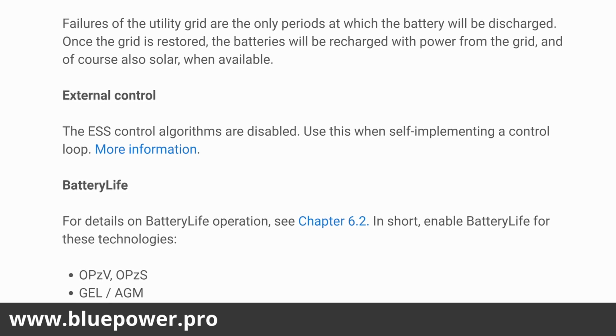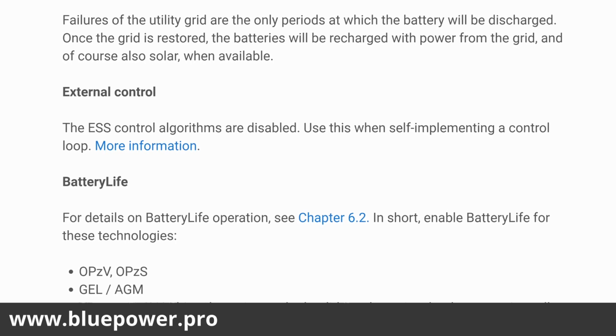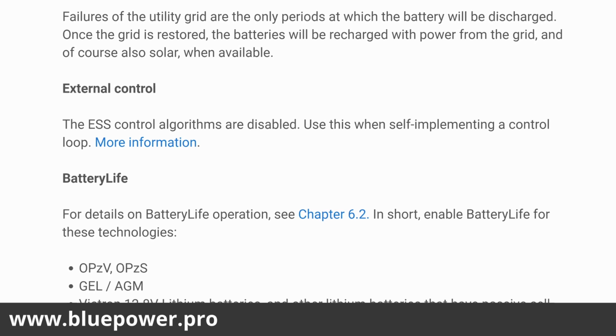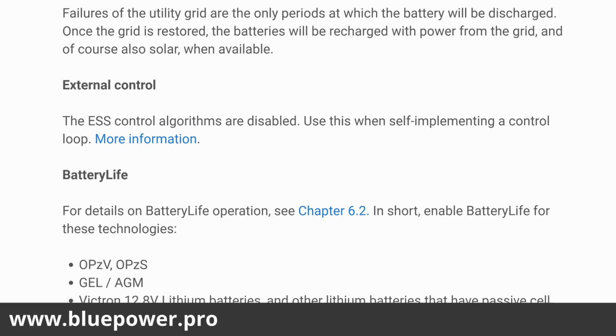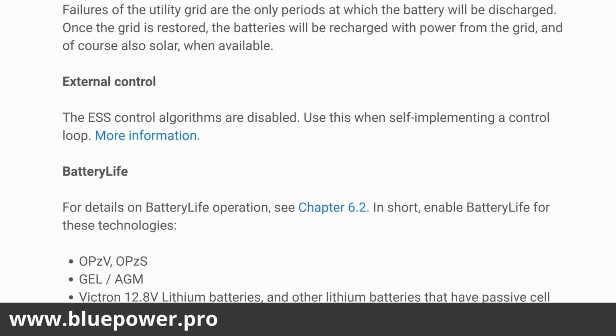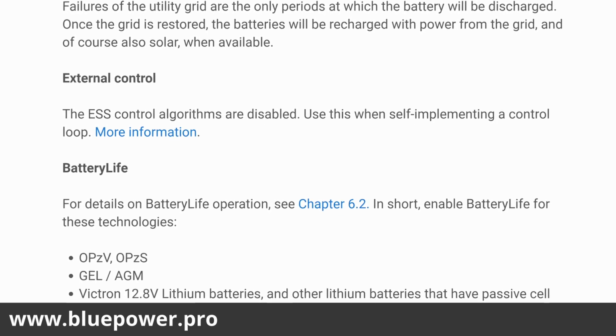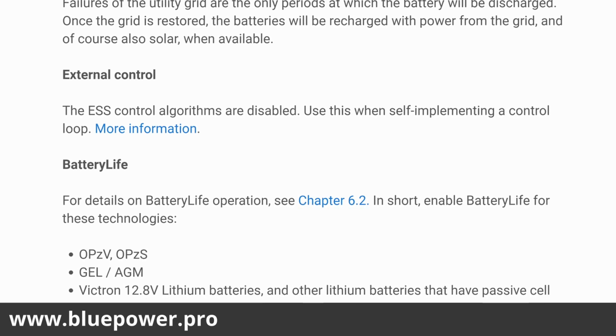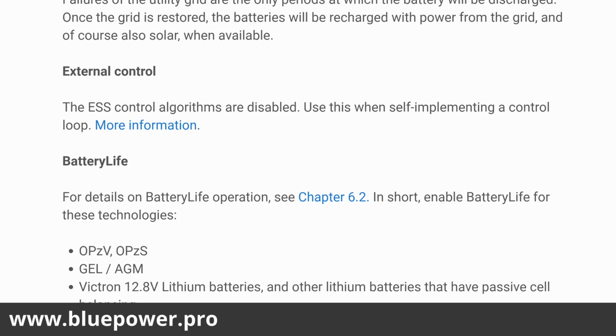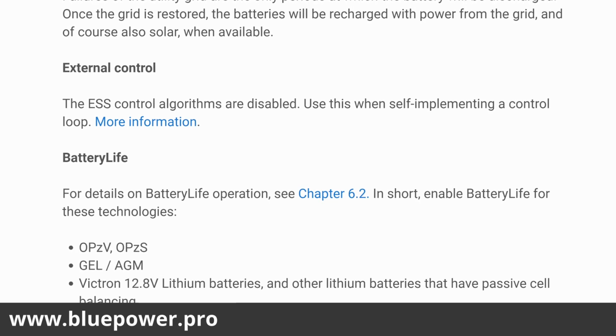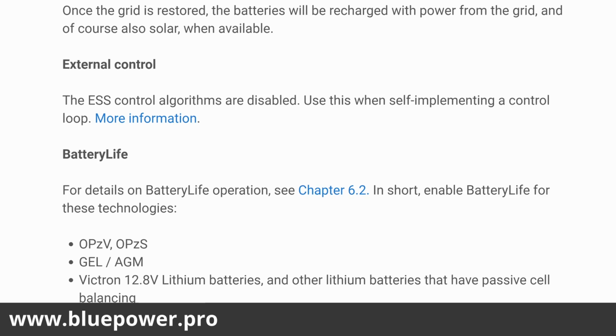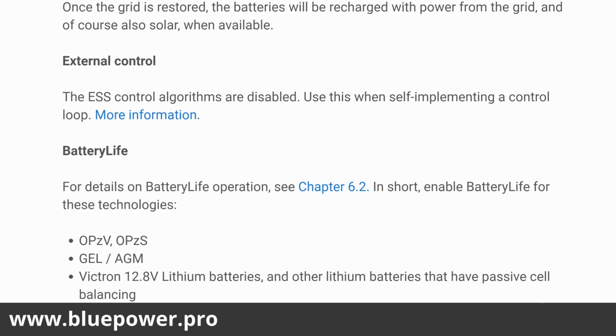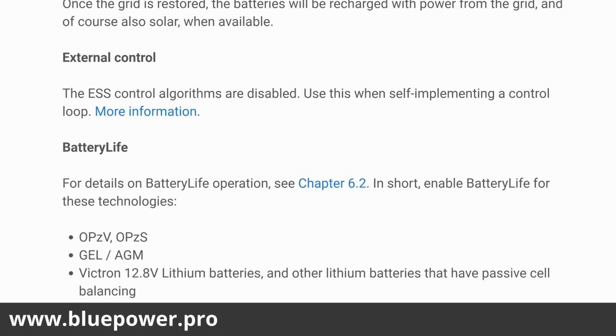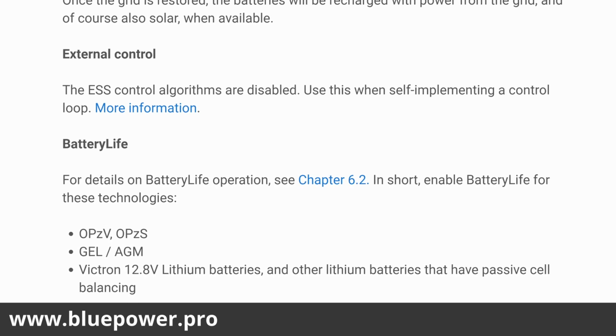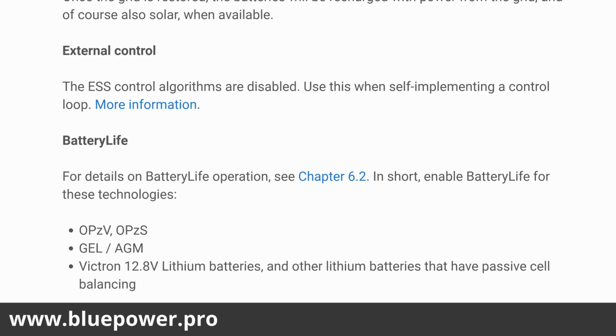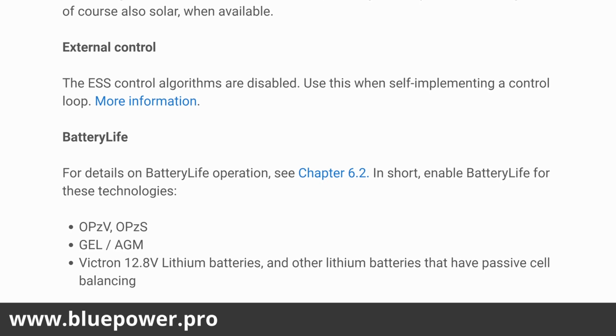It will always discharge your battery and leave it at the lower state. Optimized with battery life will always try to recharge your battery up to 100% every day. Or if the PV production really drops for 1 week, it will automatically increase the battery SOC by 5% until the battery at least receives 100% state of charge within 2 weeks' time. That's quite a long time of overcast weather, but the algorithm will always try to extend the lifetime of your batteries by keeping them closer to 100% instead of closer to the discharge value.